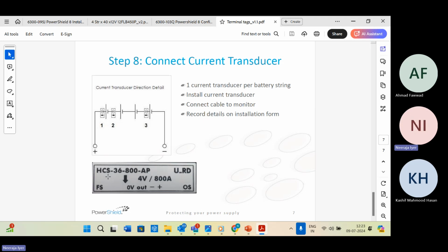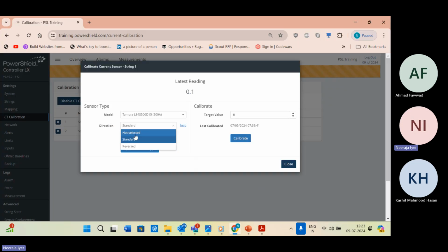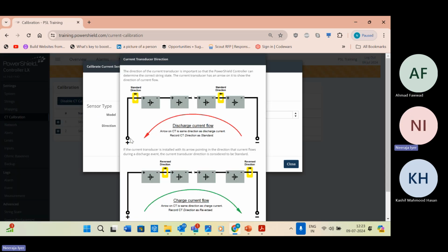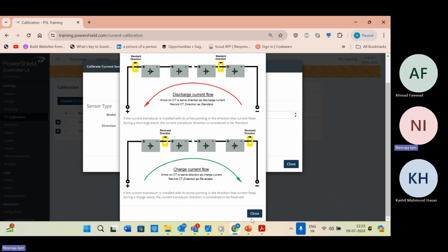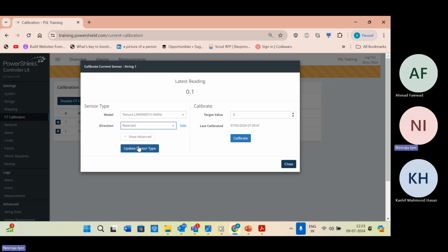See, this is the nameplate of the CT. Like you can see, there is an arrow on it. If the arrow is pointing towards the UPS positive, then in the software we select standard direction, because it is a Hall effect transducer. No problem. If it is pointing to the battery polarity of positive, no problem, you just have to select reversed. So either way is fine.